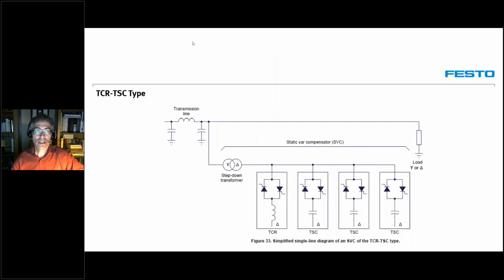The second technology is the TSC type, for thyristor switched capacitors. So as you can see, these are thyristor switched capacitors. We'll be able to insert them in and out depending on whether we trigger the thyristors or not. And with this, we don't have to compensate the full bank of three capacitors with our inductor. The inductor only needs to compensate a single bank, since each bank is added sequentially.